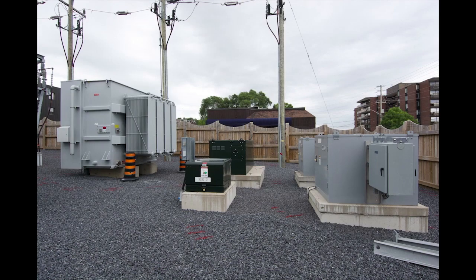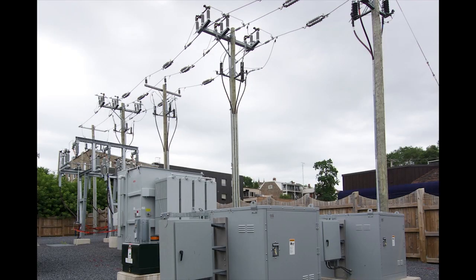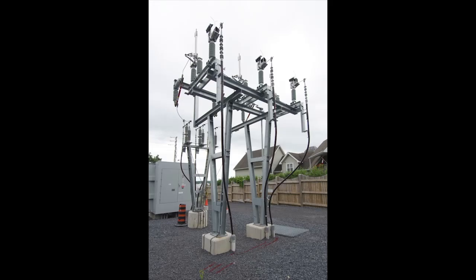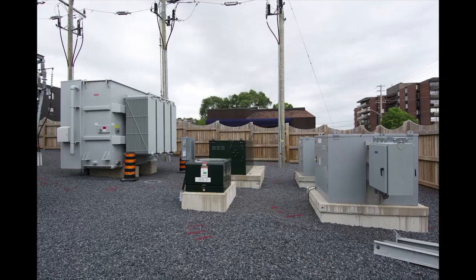At a U12 station, also referred to as a pad mount station, most of the station equipment is sitting on a concrete foundation. This includes the transformer, the switchgear that accepts the low-voltage cables from the transformer, the reclosers, and the station service transformer. Everything is connected with underground cables. The supply voltage enters the station overhead and then connects to an underground to overhead transition pole. This pole is equipped with a disconnect switch, fuse, arrestor, and cables connected to the primary side of the transformer. The feeder supply exits the station underground.